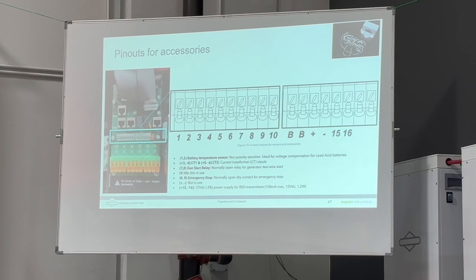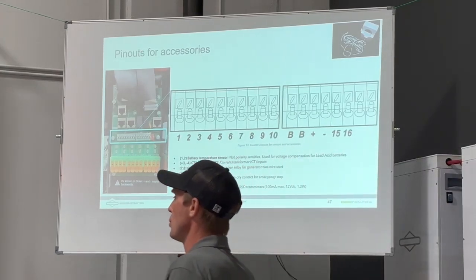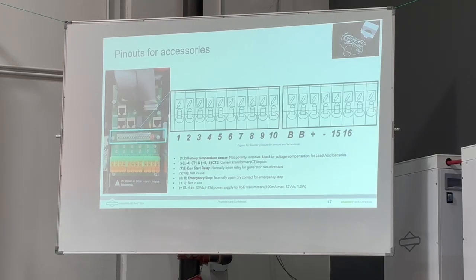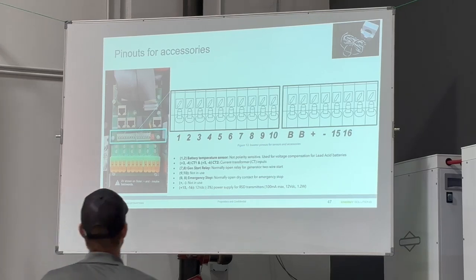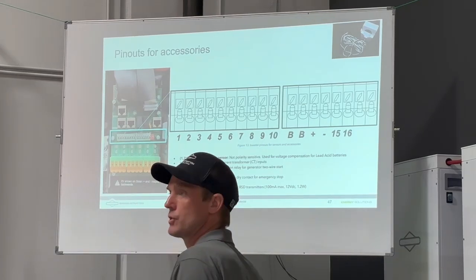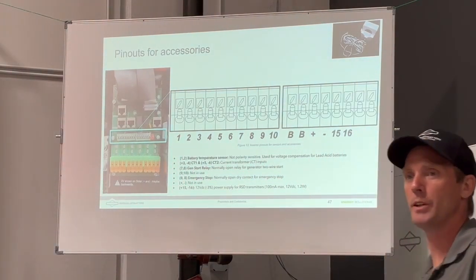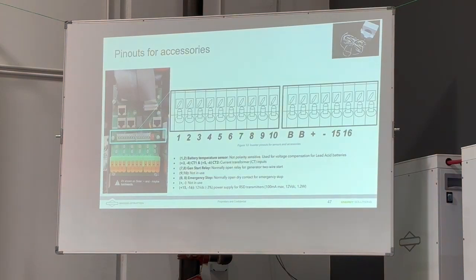Then pins 7 and 8, if you're integrating a generator and you want the inverter to be able to automatically start up the generator when the battery runs low, that's where you would use pins 7 and 8. That's your generator auto start. So that's a really nice feature. If you're using one of our Briggs Stratton generators, you disable auto main sensing in the controls. I think I have a slide coming up on that. And then you would let the Sol-Ark control the start stop of the generator.